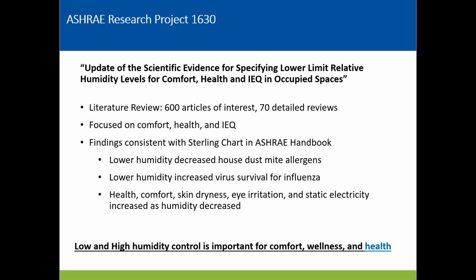And they looked at a number of articles focusing on comfort, health, indoor environmental quality, and ultimately came up with very much what was shown originally in the Sterling chart, that mid-range, that 40 to 60% had a lot of benefits for the topics we just discussed, as well as they touched a little bit on viruses. And that point on the viral survival here is quite interesting, and it's something that we're going to explore here in more detail.